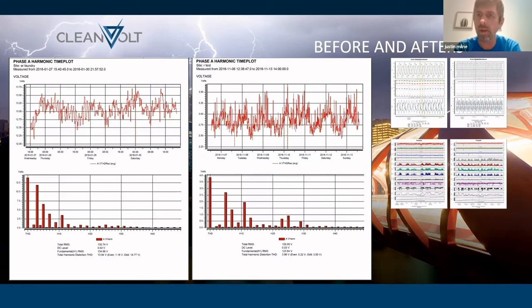And the reason we know this is because when we did the after testing, as you can see on the right-hand side, the third order of harmonic was almost wiped off the chart and now down at a level of 0.02 volts rather than 12, just under 12.5. And the reason this happened is because when we removed the energy surges from the equation, it calmed down this order of harmonic that shouldn't be present.